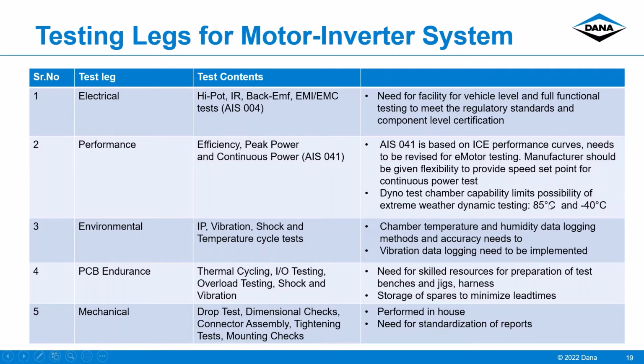When we go for environmental testing, the chamber temperature and humidity data, we should have capabilities to properly log the data and observe the test capacities, or how the device is being tested and what was happening during the test, so that we can properly do the debugging or use that test data for further analysis.